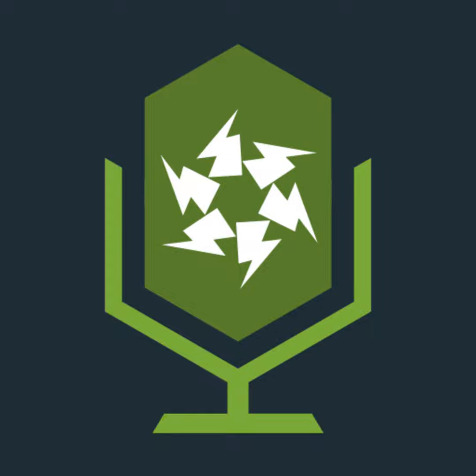So anytime we have a gas pipe, water pipe, an RSJ, or internally within the building a pipe that re-enters the ground and then resurfaces, it still needs to be checked that it's a new reference of 0 entering our equipotential zone, and we bond the crap out of it. That's when we choose to bond it.